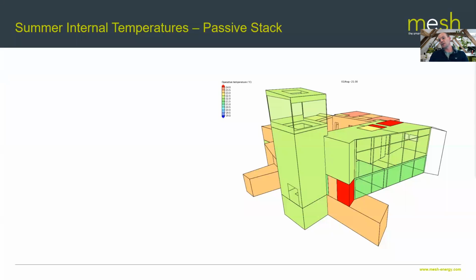So we modeled this building in our software as well. Funnily enough, it was actually modeled after the building was built. So they went about this in a kind of backwards way. But this goes to show you analytically how this works. And this result here is for assuming these opening windows and the roof lights working and cross ventilation, and shows a particularly cool building, actually.